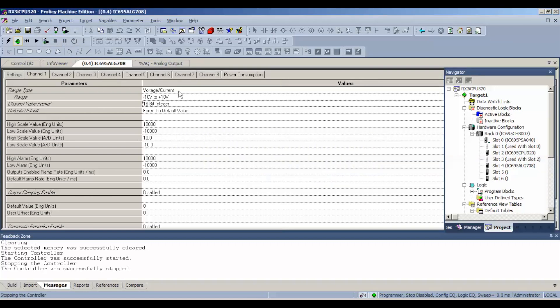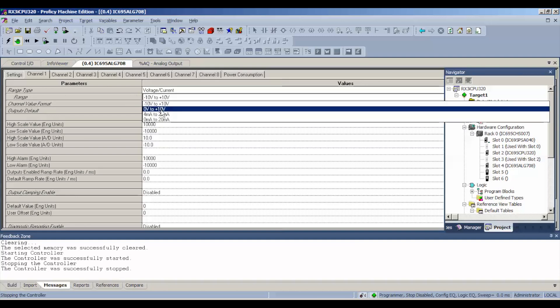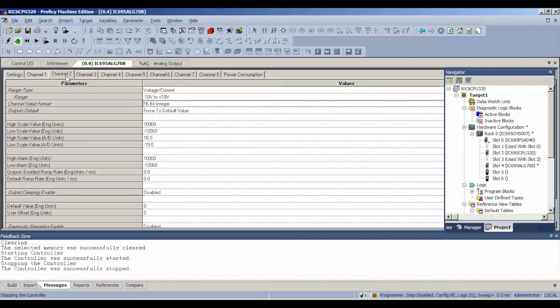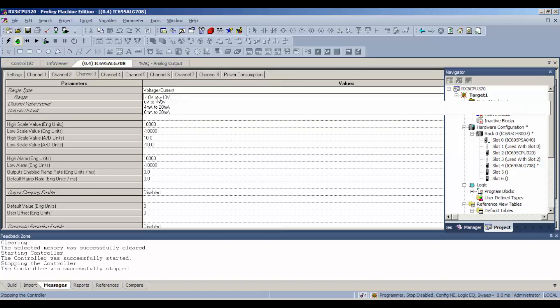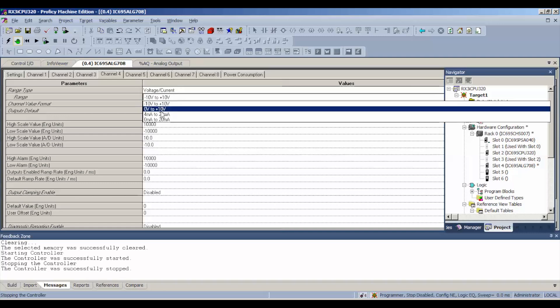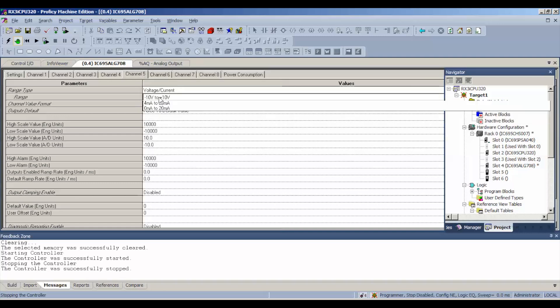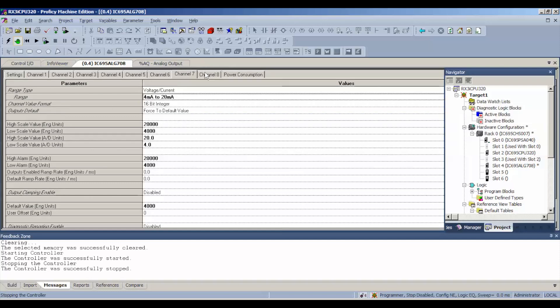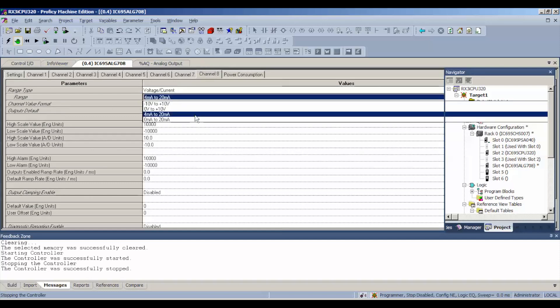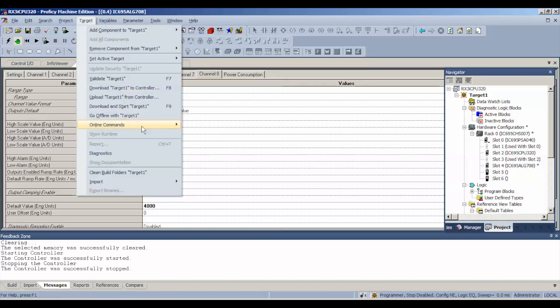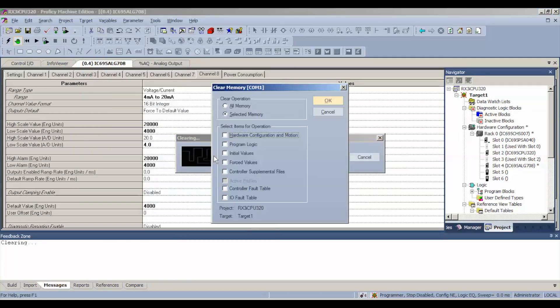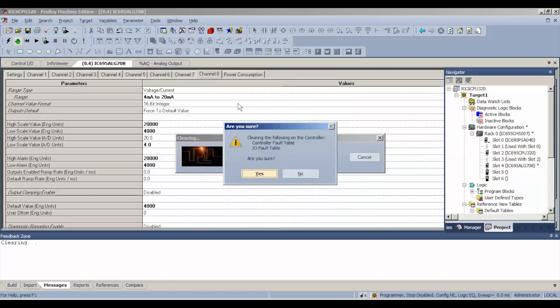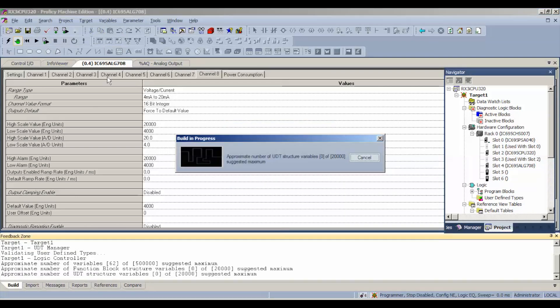We're going to stop the outputs. Go to channel one. We're only going to change one thing and that is we're going to edit the range. If you look at my arrow here, you see where I've got on the other side of range. It's editable. You can open it up and do 4 to 20 milliamp. I prefer to do all eight channels even if you're not using them all. Just make sure it's a completely good working device. Same thing. You're asking it to do something slightly differently. Before we were doing the voltage, so you want to go to online commands, clear. We want to clear the controller and IO fault tables because we're faulted now. We're asking it to measure milliamp or output milliamp, which is different. We're going to say okay and we're going to download that information.